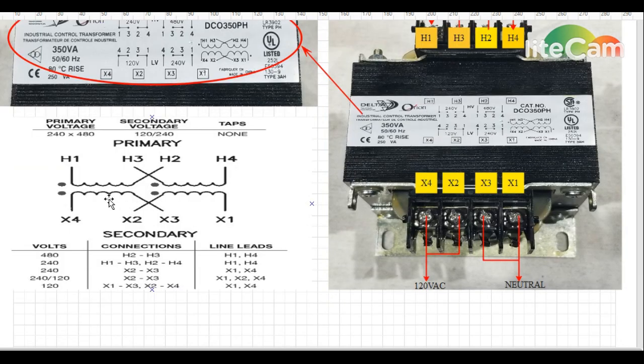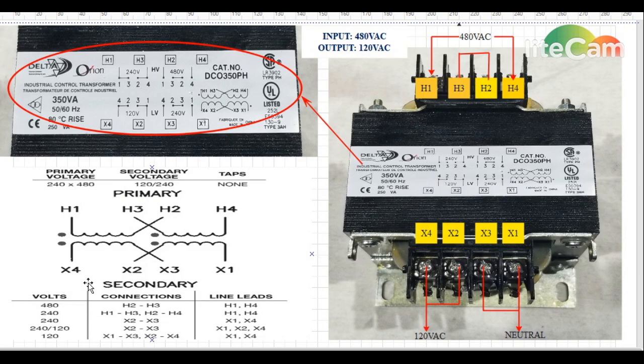Same thing with the drawing at the bottom. If you have to wire to 240 voltage, we need to connect H1 and H3 together, H2 and H4 together, and our main line leads will be coming to H1 and H4. The only difference will be the voltage. So that will be our 240 voltage coming as the main voltage to the transformer on the primary side.